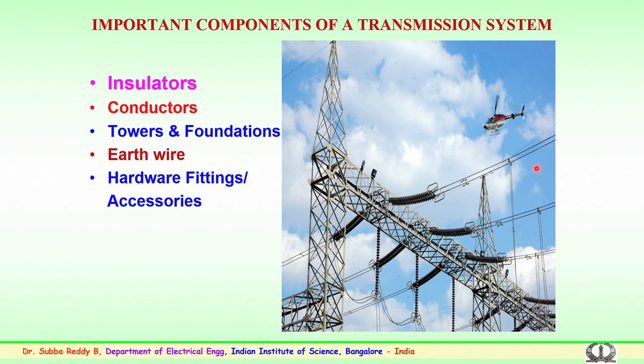The conductors for up to 132 kV systems could be a single conductor, for 220 kV it could be a twin conductor, for 400 kV there could be a 4-bundle conductor, and above 400 kV, at 765 kV, it could be a 6 or 8 conductor bundle.